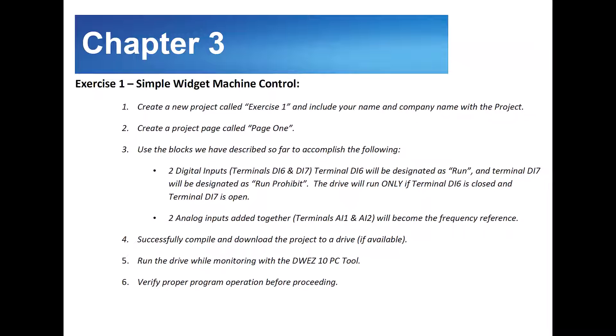We will use the blocks we've described so far to accomplish the following. We want two digital inputs. We will be using terminals DI6 and DI7. Terminal DI6 will be designated as a run and terminal DI7 will be designated as a run prohibit. The drive will only run if terminal DI6 is closed and terminal DI7 is open. That will handle our run.